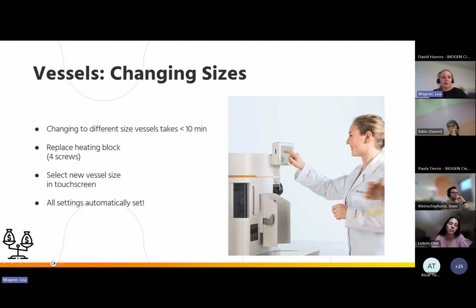The vessels can also be changed easily. Between the 3 different vessel sizes, we have 1.5 liters total volume, 3 liters and 6 liters total volume for Minifors 2. And changing the vessel sizes takes less than 10 minutes because it's very easy. You just have to remove and exchange the heating block, of course, because the vessel will be smaller or bigger, and then the customer can select the new vessel size on the touch screen, and all settings are automatically set. So this saves the customer working time, and less equipment is needed, because the customer can change between vessel sizes by themselves and does not need the service to come to change configuration, but everything is set automatically.